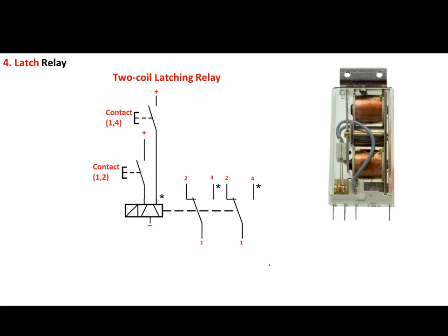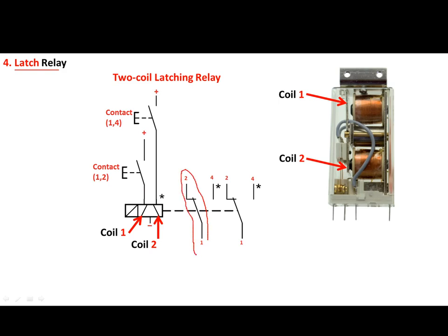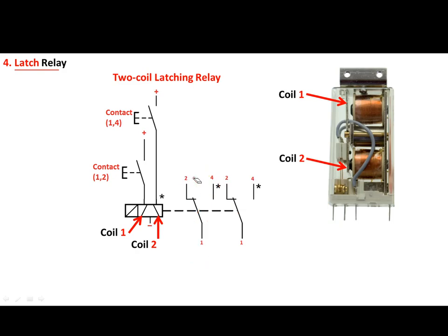The fourth signal storage method is the latch relay. A latch relay is an interesting component with dual coils — coil one and coil two. When a push button is connected to the first coil and a second push button to the second coil, this causes the relay to have two states depending on which push button is operated.